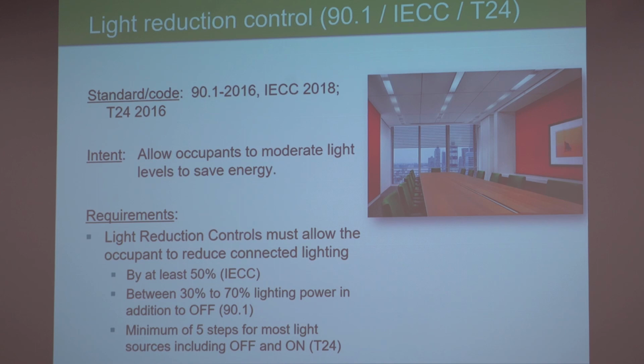Any electric lights that are in that zone, that's a daylight zone. And if lights are partially in a daylight zone, so just half of the light fixture is in the daylight zone, you still have to control it. Or even if it's just a quarter of the fixture in the daylight zone, you have to control it automatically.